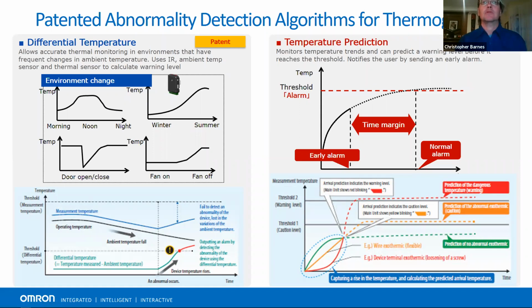Continuous monitoring also lets you catch things using prediction, basically by looking at the rate of rise. The nice thing about continuous monitoring is if you checked an electrical panel and got a reading of, say, 30 degrees when ambient temperature was 25 degrees, you might think that's no big deal, it's just running a little warm. But if you're measuring constantly and see it ramping up exponentially, it can trigger the alarm at 30 degrees, even before it crosses a threshold, just by seeing the rate of acceleration. So continuous monitoring lets you catch a short circuit or something going wrong earlier, because the temperature is rising rapidly.